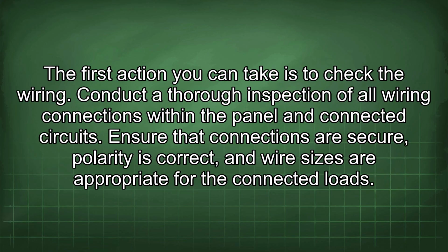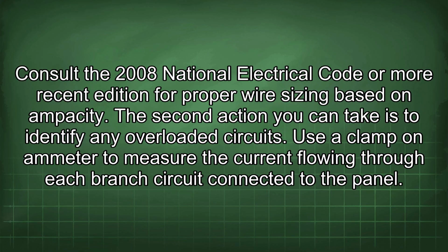The first action you can take is to check the wiring. Conduct a thorough inspection of all wiring connections within the panel and connected circuits. Ensure that connections are secure, polarity is correct, and wire sizes are appropriate for the connected loads. Consult the 2008 National Electrical Code or more recent edition for proper wire sizing based on ampacity.